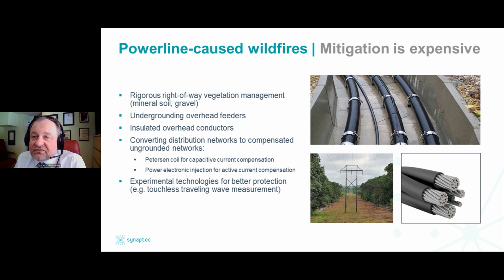So obviously you start with rigorous right-of-way vegetation management. Ideally, you would like to use the right-of-way as a fire break. That means that you may clear vegetation all the way to mineral soil or even apply gravel. Undergrounding overhead feeders is contemplated. This is not only expensive, it would also take a very long time to convert all our feeders into cable circuits. Insulated overhead conductors are something in between, so you retain the infrastructure of the poles and the right-of-way the way it is, but you cover the conductors with a dielectric.